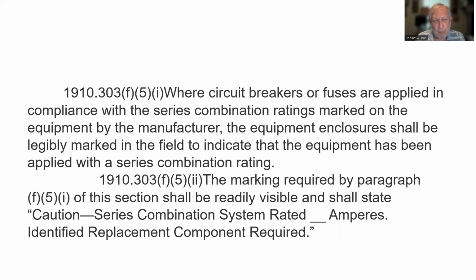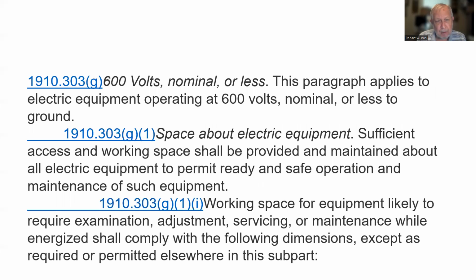Marking for series combination ratings. Where circuit breakers or fuses are applied in compliance with the series combination ratings marked on the equipment by the manufacturer, the equipment enclosures shall be legibly marked in the field to indicate that the equipment has been applied with a series combination rating. The marking required by paragraphs above this section shall be readily visible and shall state, caution, series combination system rated, blank amperes, identified replacement component required. 600 volts nominal or less. This paragraph, 303G, applies to electric equipment operating at 600 volts nominal or less to ground.